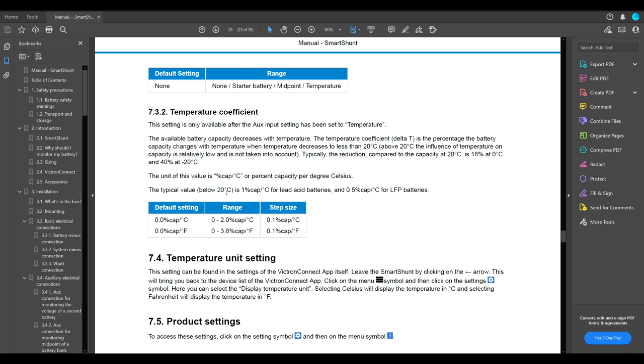The typical value below 20 degrees Celsius is 1% of capacity per degree Celsius for lead acid batteries. And 0.5% capacity per degree Celsius for lithium iron phosphate batteries. As the beginning of this adventure of guesstimating the capacity, I'm going to put it as it is recommended in the instruction manual. I will monitor it over a period of time. And if I see that I need to adjust this number, I'm going to post a video about that. But normally, these settings will probably guesstimate properly during the year.